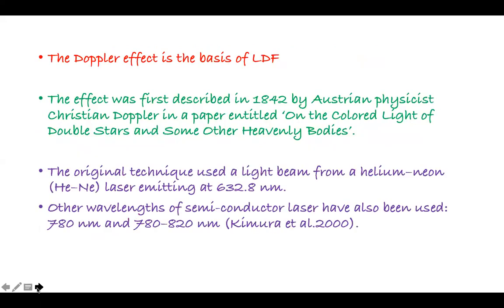The Doppler effect is the basis of laser Doppler flowmetry. This effect was first described in 1842 by Austrian physicist Christian Doppler in a paper entitled 'On the Colored Light of Double Stars and Some Other Heavenly Bodies.' This technique uses a light beam from a helium-neon laser with a wavelength of 632.8 nanometers. Other wavelengths used are semiconductor lasers with wavelengths of either 780 nanometers or 820 nanometers.